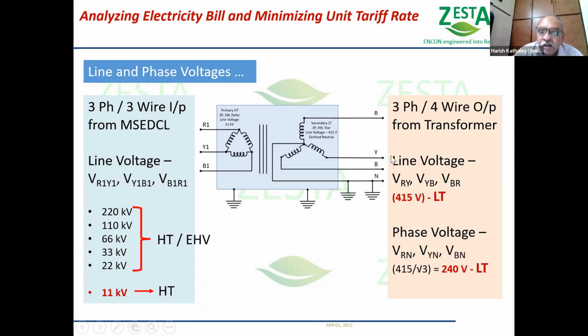The phase voltage means R and neutral, Y and neutral, B and neutral. It is 415 by root 3, that is 240 volts. This is what we are using.